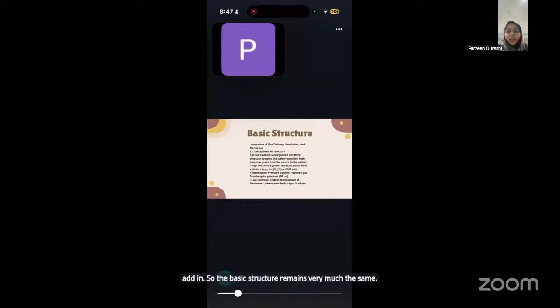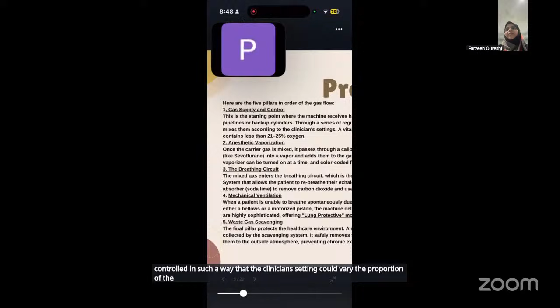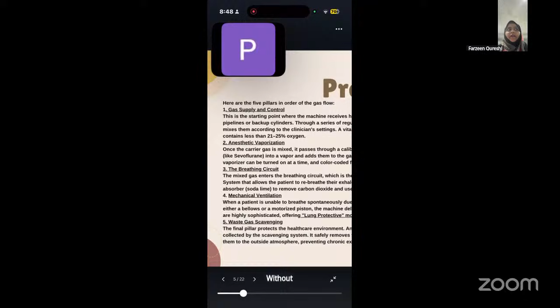So what changed? The process of change went into the 5 pillars, in order of the gas flow. First, the gas supply. We had the gas supply controlled in such a way that the clinician setting could vary the proportion of the gases actually getting delivered to the patient. And there was no less than 21 to 25% oxygen going to the patient in all cases without exception.